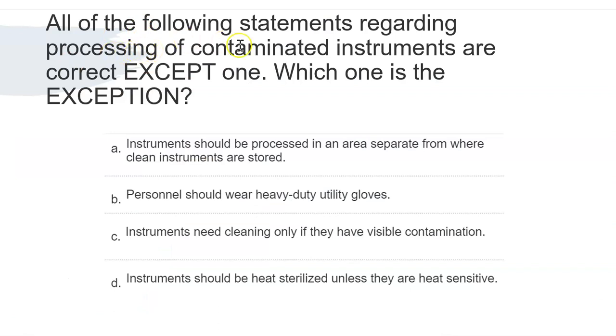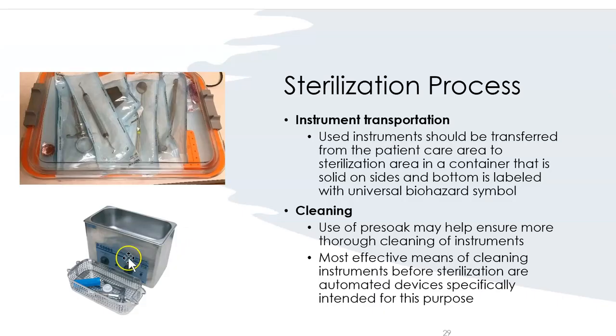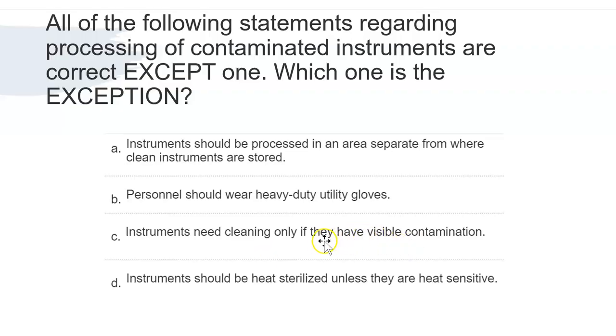Question: All of the following statements regarding processing of contaminated instruments are correct except one. The answer is C: instruments need cleaning only if they have visible contamination. That is incorrect — instruments must be cleaned to remove bio-burden and deposits before sterilization, regardless of whether contamination is visible or not. We clean them every time.